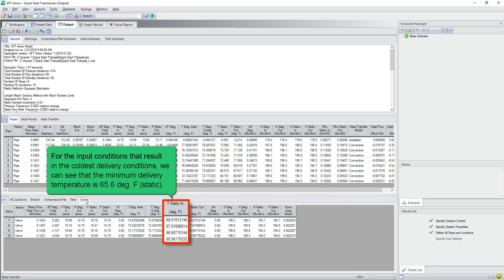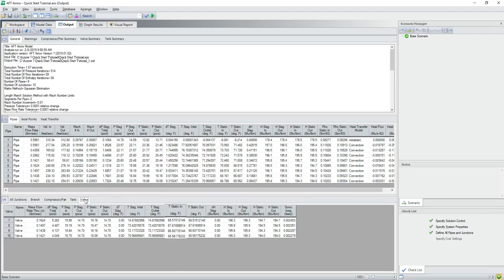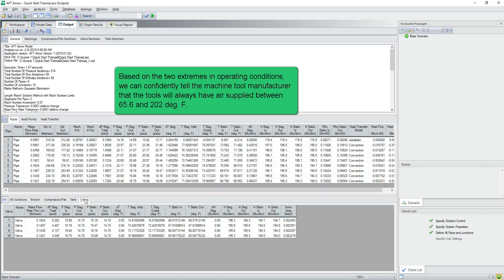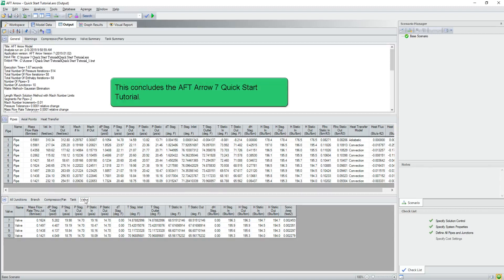For the input conditions that result in the coldest delivery conditions, we can see that the minimum delivery static temperature is 65.6 degrees Fahrenheit. Based on the two extremes in operating conditions, we can confidently tell the machine tool manufacturer that the tools will always have air supplied between 65.6 and 202 degrees Fahrenheit. This concludes the AFT Arrow 7 Quick Start Tutorial.